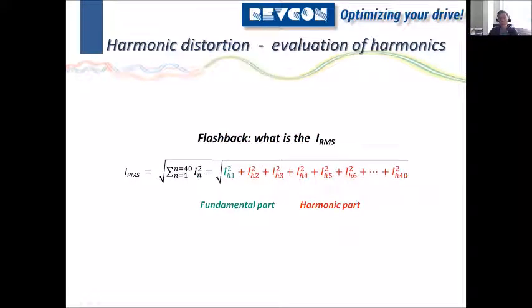Before we have a look at the equation for total harmonic distortion, I would like to give you a quick flashback to what the IRMS is. The IRMS is typically what you would measure with a standard clamp meter when you measure the current in any kind of application. This has two parts. The first part is the fundamental part. That's the sine wave part of this input current. That's the friendly part. Then we have the harmonic part, which is an overlapping part. That is the part that is causing harmonic currents. So this IRMS is altogether the fundamental and the harmonic part.